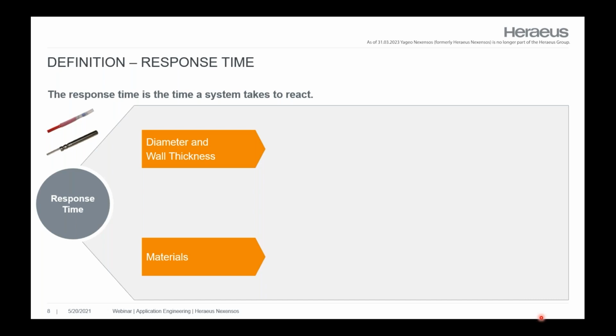Let's start with the first factor here, the diameter and the wall thickness. All in all, you can say that the more material you have around the sensor, the slower the response time. You have here a drawing example, and you can see directly there's a lot of material around our sensor element. That would result in a bad response time.